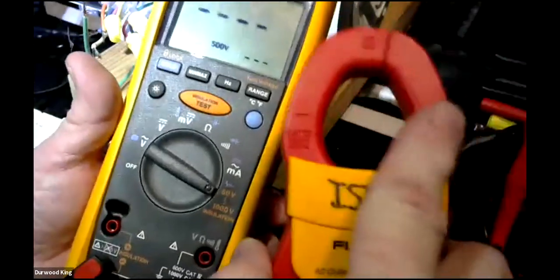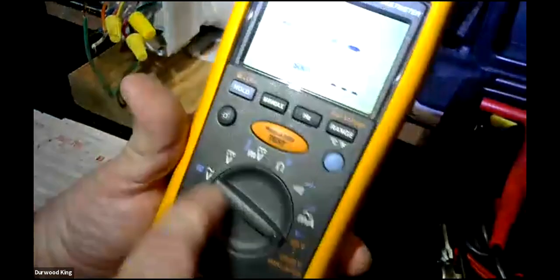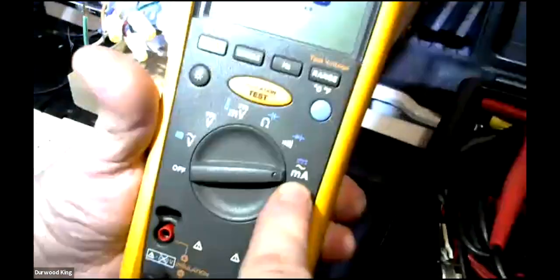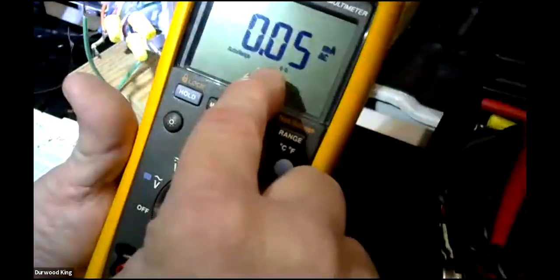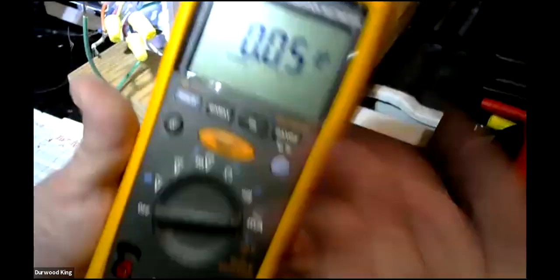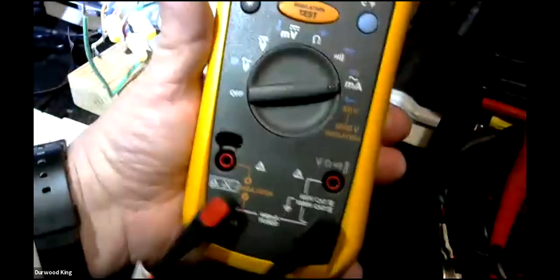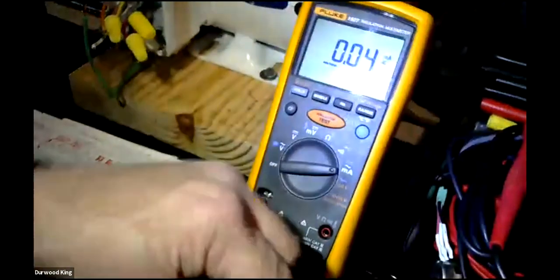So this probe steps 1 whole amp down to 1 milliamp. So you would put this on milliamps, and for every amp that you read here around a motor lead, when you clamp it, it would say 1 milliamp. So if it was 10 milliamps, it would be 10 amps. Okay. So that attachment is what you can use on that meter for checking amps. But that's not what we're doing right now. I'm just showing you what it'll do. So all that comes in your accessory kit if you get the whole thing.